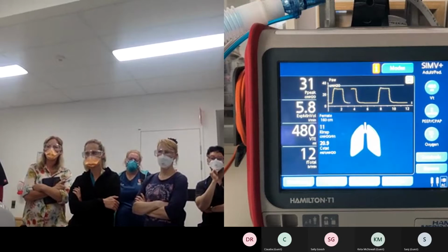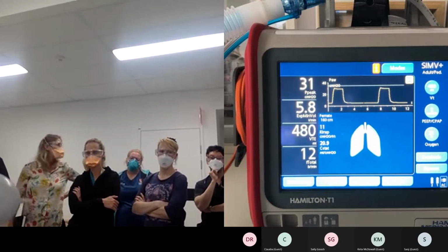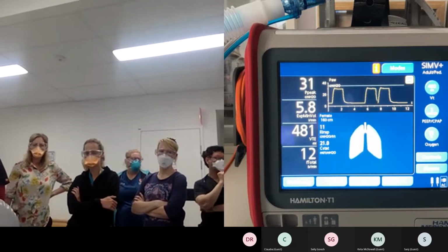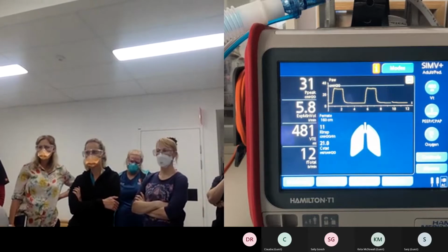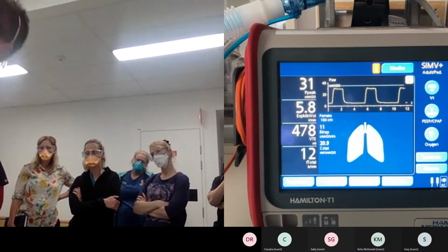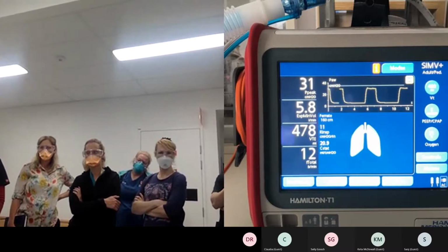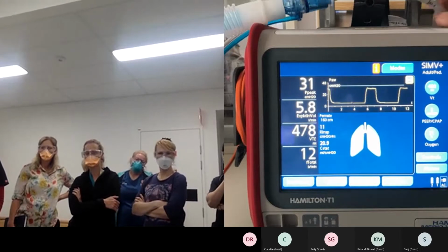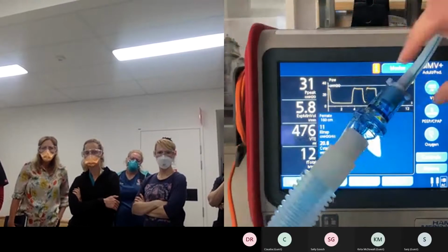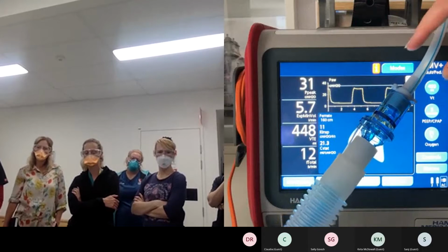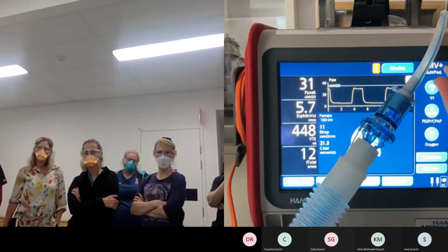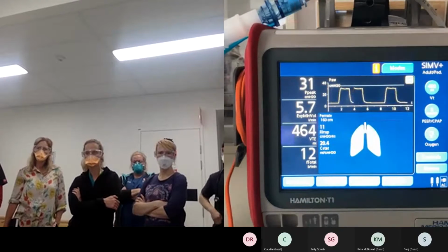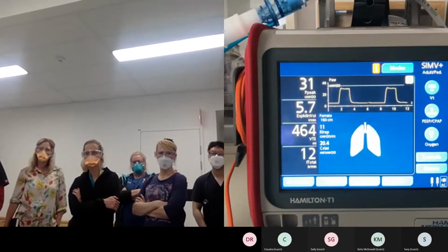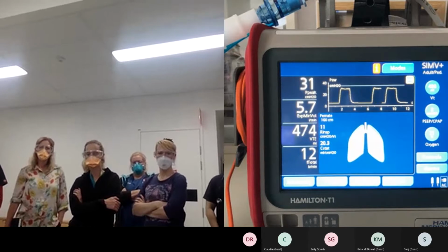And then you've got your spray can. If you do use the nebulizer port on the side, you'd put your oxygen tubing over to the yellow port, and your T-piece would come into the circuit. So you'd have an HME, and then you'd have your T-piece with the medication chamber underneath it. And then you would touch on this to start running it. Okay, it runs for 30 minutes on inspiration only.